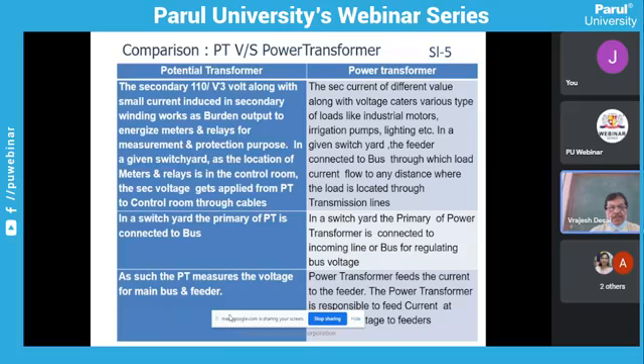In a CVT or PT in the switchyard, the primary of the PT is connected to the bus, and the PT measures the voltage on the main bus and feeder. Whereas in a power transformer, the secondary current is proportional to the feeder's requirement. It is connected to the bus through various load feeders, and power flows to various distances. In a switchyard, the primary of the power transformer is connected to the incoming line or bus for regulating bus voltage. As we have seen in the previous slide, in the layout of the substation, the power transformer will feed the current to the feeders, and it is responsible for feeding the current at all the feeders connected to it.